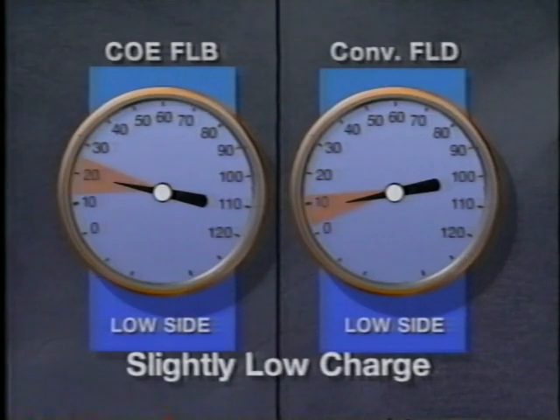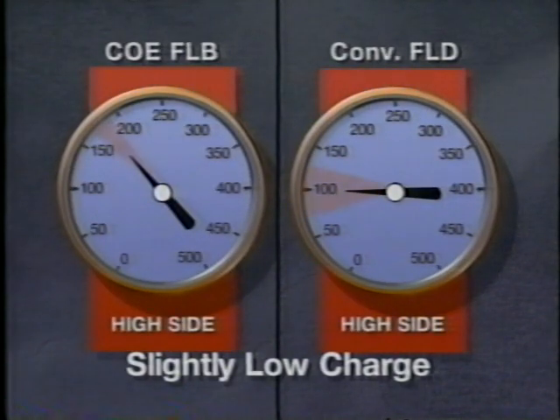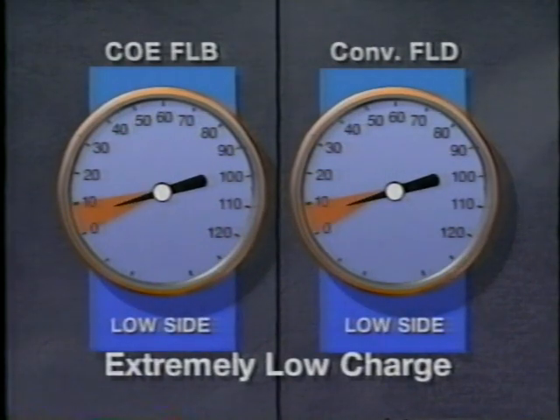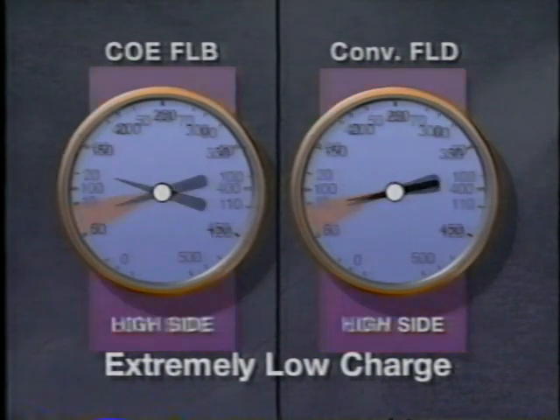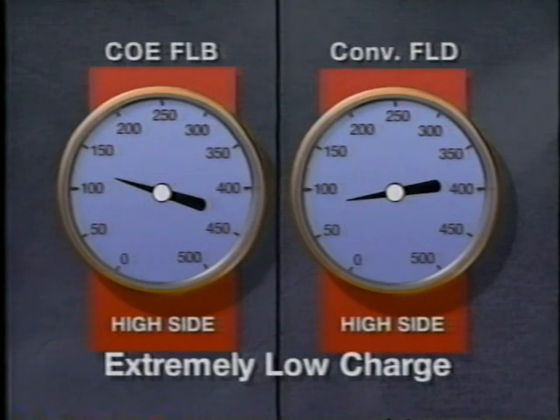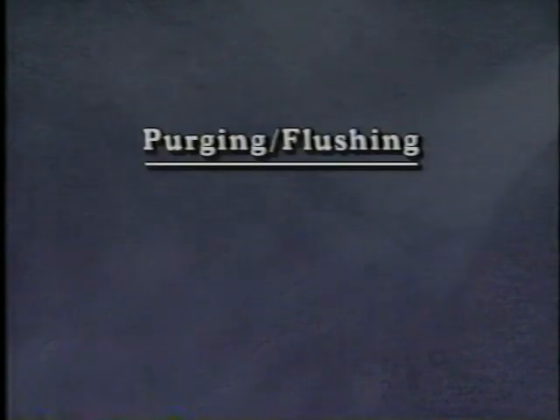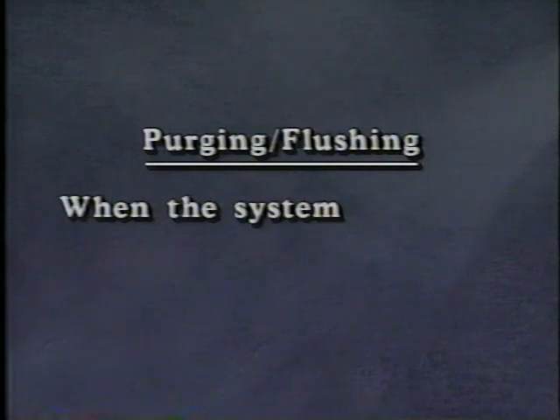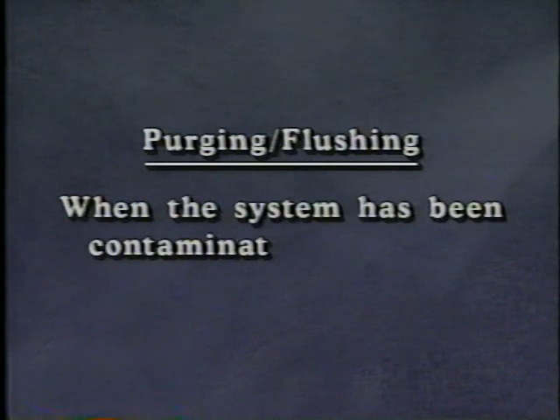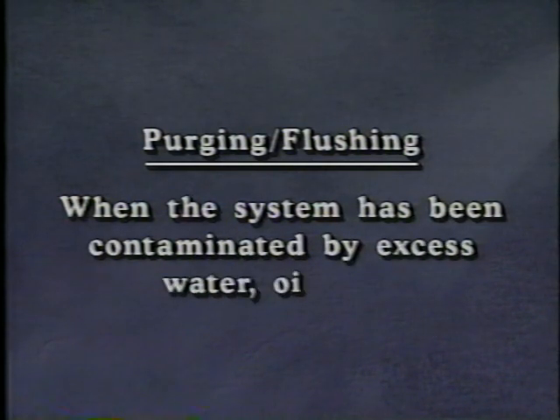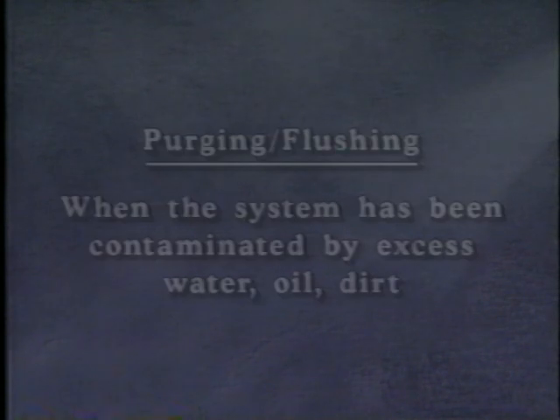Low gauge readings indicate the system is low on refrigerant. An extremely low charge will be indicated by lower gauge readings. Some gauge readings, examples of which we'll see in a moment, may indicate the necessity to purge or flush the system. If a sample of oil from the compressor shows it has been contaminated by excess water, oil, or dirt, the system must be purged or flushed.